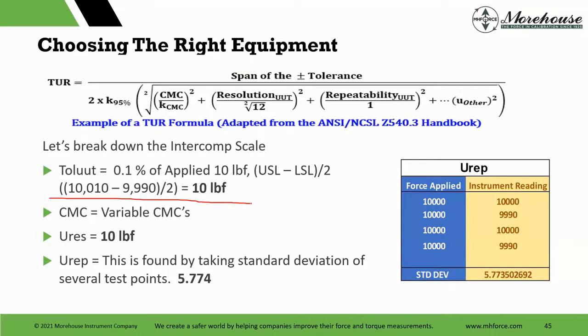So tolerance is easy. CMC, who cares? That's our calibration and measurement capability. We're going to care eventually, but we don't care in this one because the problem here is the resolution. The resolution matches the uncertainty. So resolution is 10 pounds, and repeatability is found by taking the standard deviation of several test points. The more test points you take, the more it costs you as the cal provider, the better you can get this for the customer.